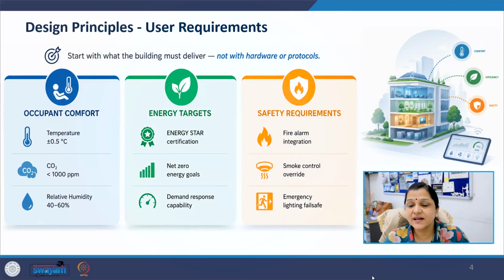Design principles as per user requirement. The first principle in building automation system design is very important. The building owner and users must first define what the building is expected to deliver. For occupant comfort, the designer may define temperature control within plus or minus 0.5 degree Celsius. Indoor air quality may require carbon dioxide level below 1000 ppm. Relative humidity may need to remain between 40 to 60%.